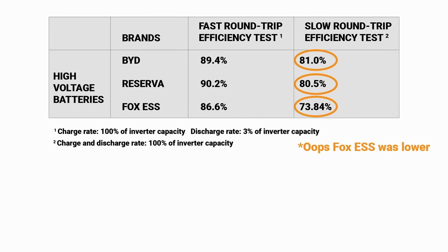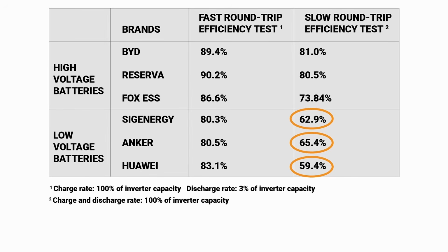74, 75 - I mean, if we compare that to, let's not pick on Sig, let's use Anker as an example - all three of these DC to DC converter batteries are down at 63%. So the real world comparison of the efficiency you get is 74% for the high voltage batteries versus all three of these batteries being very close to 63%. So it's not a measurement issue - you're losing over 35% of your battery capacity just in those conversion losses.